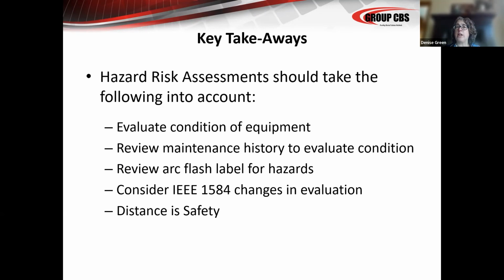Remember to review those arc flash labels for dates and potential hazards with the equipment that you're working on, and consider those changes in IEEE. And then always remember, distance is safety. The further we can get away from that arc flash event when we're doing our switching, be it whatever tool we use, whether a remote racking tool, a remote switching tool, a mimic panel, whatever the case may be, the further you get away from that arc flash potential, the safer you are. So any other questions? Hope I crammed it all in time.